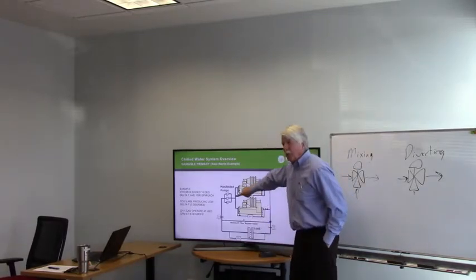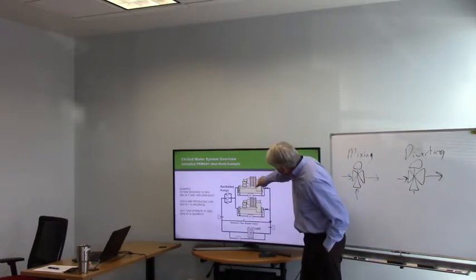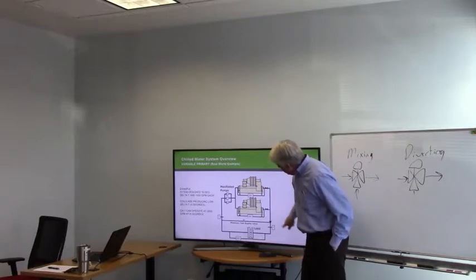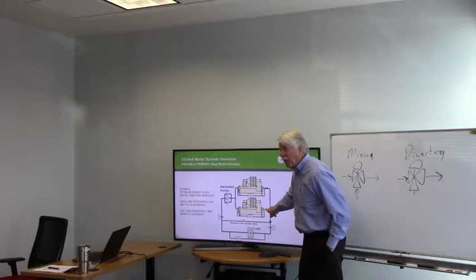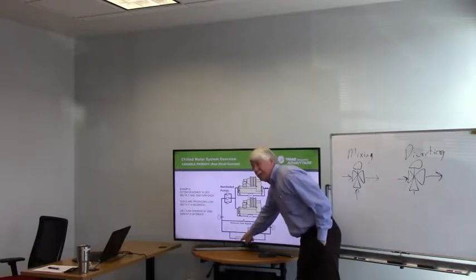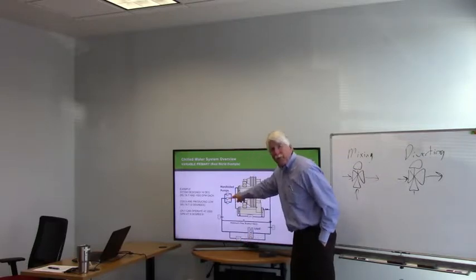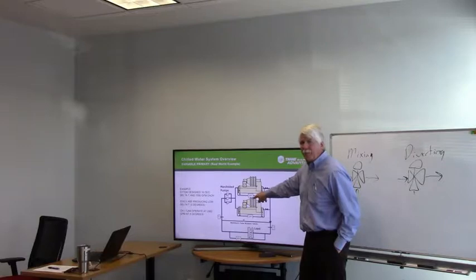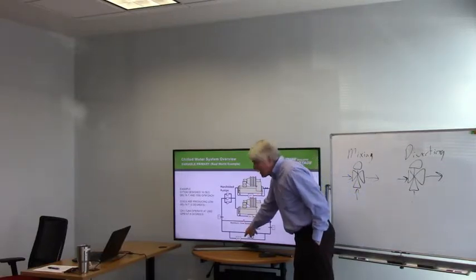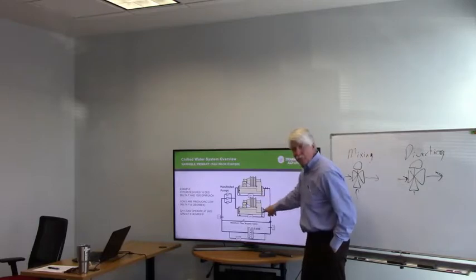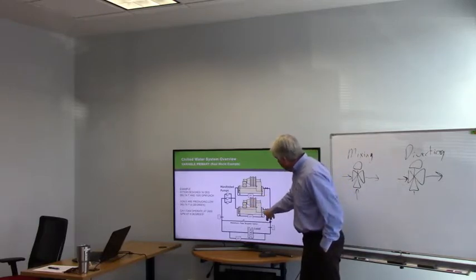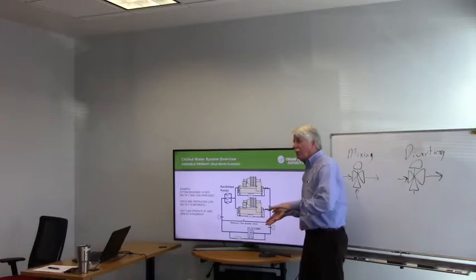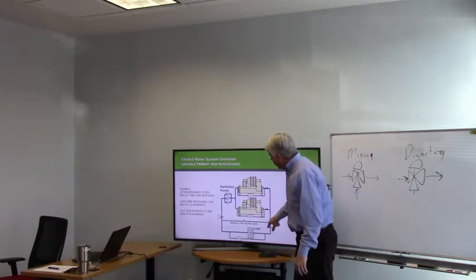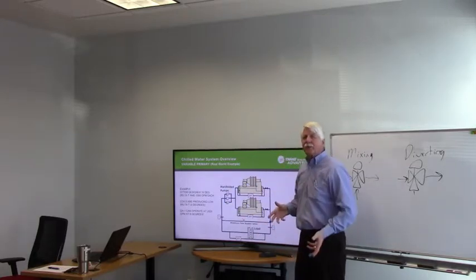When you think about it, we're running one chiller and we want to bring on a second chiller. So I've got established flow through here. Now, as soon as I start cracking that valve open, this DP will see it, and that DP should speed up the pumps, okay? But it's important that this guy have time to react while this one is moving. Now, if we make this valve real slow, it gives the system lots of time to react. So it only steals a little bit of water, the pumps speed up and everything works really good.